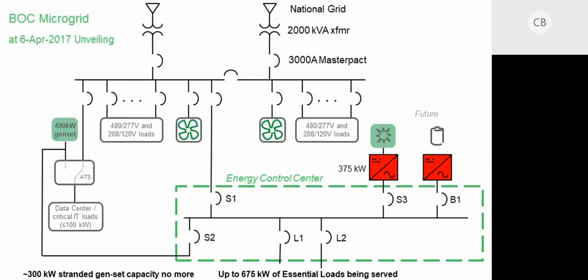So we tied off the output of the generator to feed this energy control center. So now if we lose utility power, we have the ability to back up these other services within the building outside of the data center environment with 300 kW of generator capacity. We have the solar and battery energy storage. It also gave us the ability to leverage this solar power and battery energy storage to do some peak demand shaving in the building. And so we get a benefit of reduced utility consumption throughout the cycle. Next slide, please.